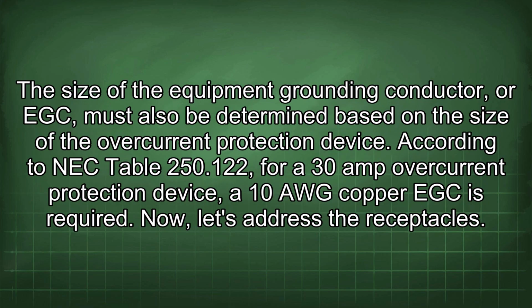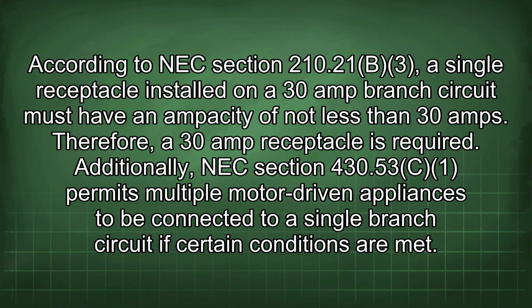The size of the equipment grounding conductor, or EGC, must also be determined based on the size of the overcurrent protection device. According to NEC Table 250.122, for a 30 amp overcurrent protection device, a 10 AWG copper EGC is required. Now let's address the receptacles. According to NEC Section 210.21(B)(3), a single receptacle installed on a 30 amp branch circuit must have an ampacity of not less than 30 amps. Therefore, a 30 amp receptacle is required.